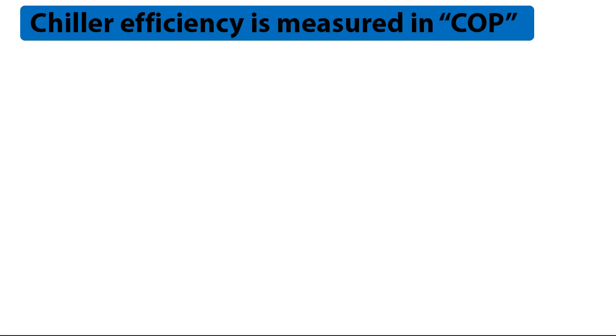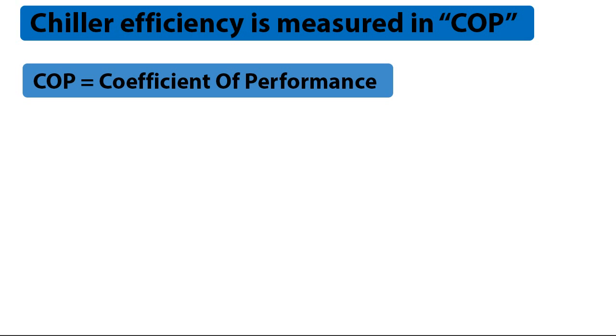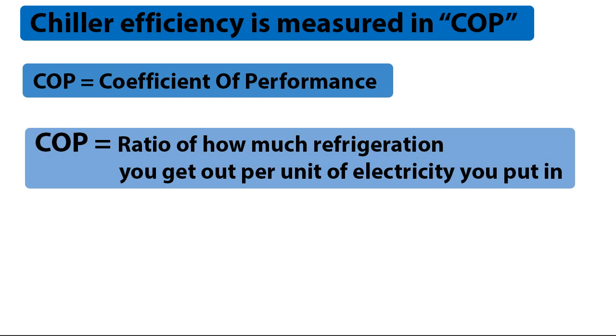Chiller efficiency is measured in COP. The COP stands for coefficient of performance, and really the COP is the ratio of how much refrigeration you get per unit of electricity that you put in — into the compressor and the controls and anything that goes with it. Really all the electricity that goes into that chiller and how much refrigeration you get out of that chiller.